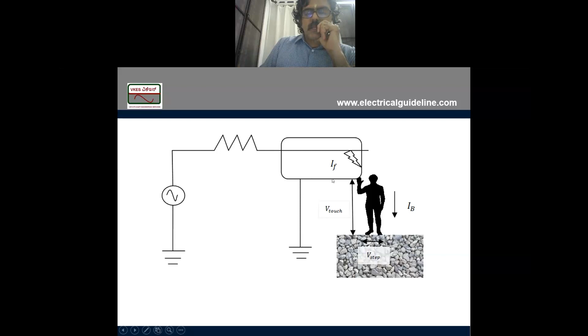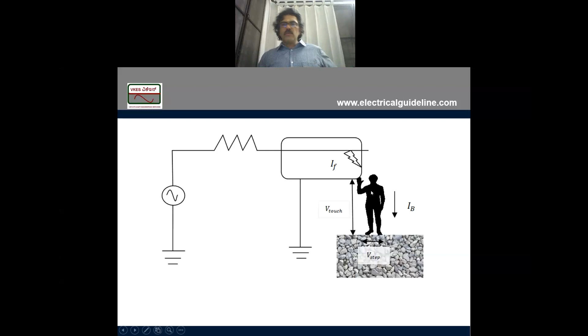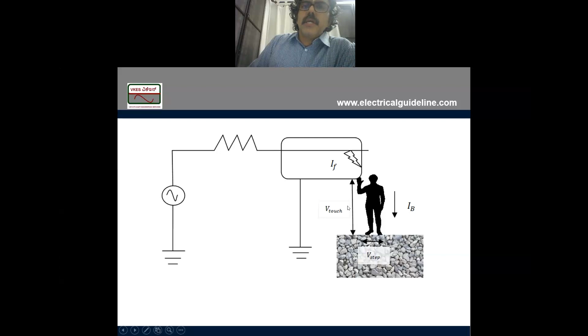Now the potential of this depends on this fault current and the resistance here. Now see this person, if he touches this non-conducting metal, which during a fault becomes conducting, this fellow will get an electric shock. And if the current through his body is more than 116 milliamps, please note this value, 116 milliamps, but this value is as per IEEE 80. If you go for BS or some other standard, there may be some changes in the value. Now when this current flows through this person, if it is 116 milliamps, then he gets an electric shock and he may die. Now this voltage is what we call the touch voltage, right?